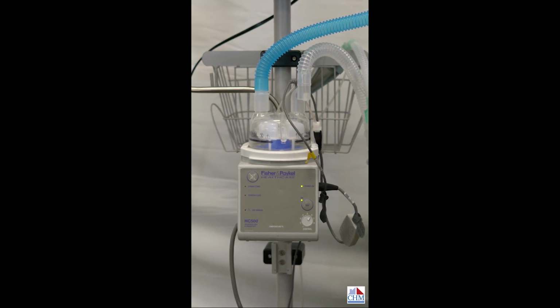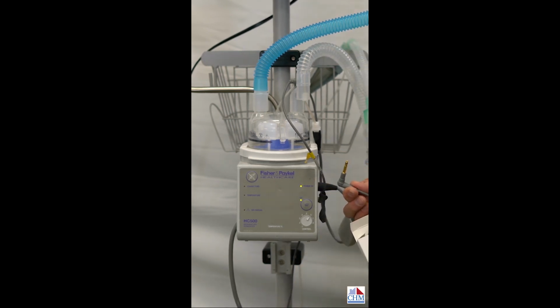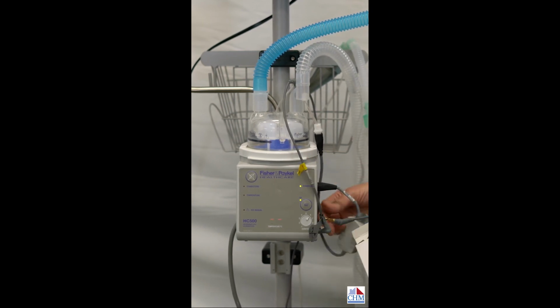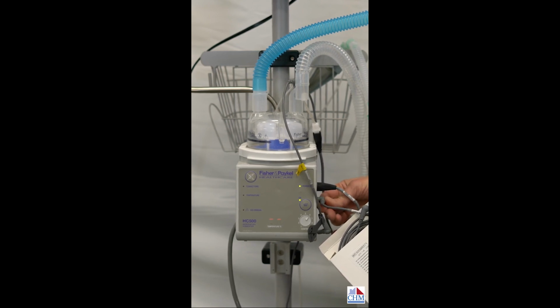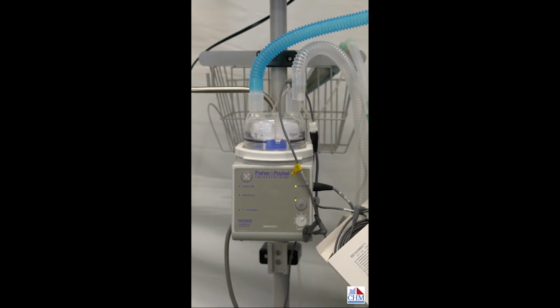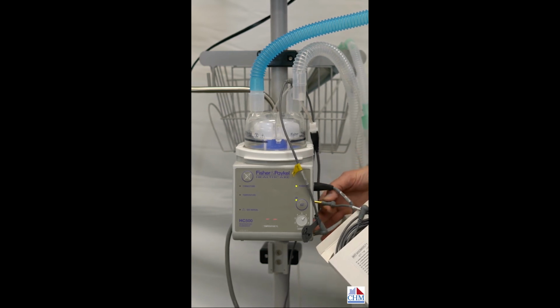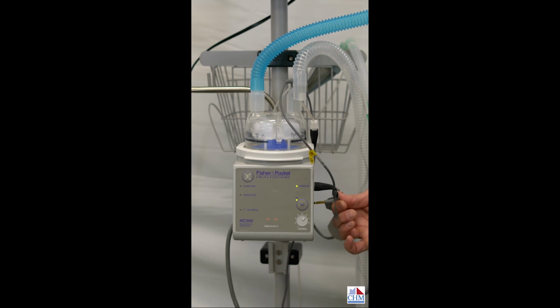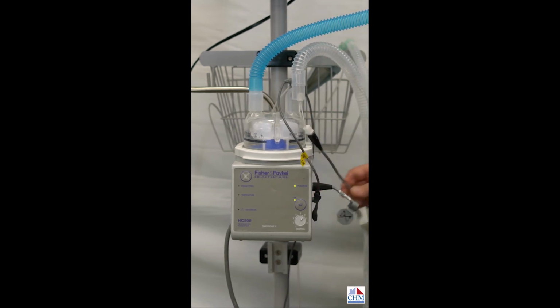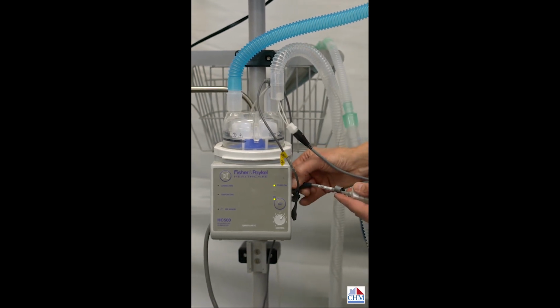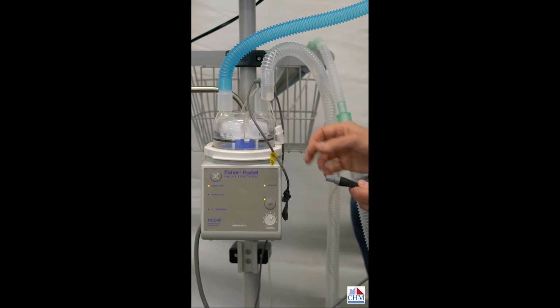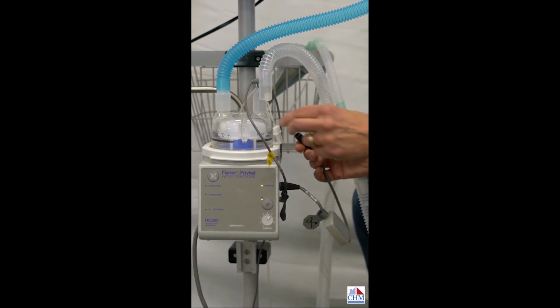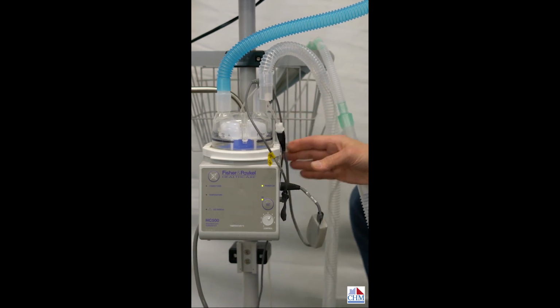Now the easiest thing to do that I would recommend, rather than changing the whole temperature probe wire, is to just take a new one out of the box like this and take that end and plug it into the side. You don't have to take it out of the circuit to start with. That'll save you some time. And if you find that doing that corrects the problem, now you can go ahead and change the entire wire. But if that was not the problem, we would move on to the next possibility, which would be the heated wire adapter. So the heated wire adapter, you would just simply remove, grab a new one, and place that in the circuit like that. And of course that would stop the alarm if that was the issue.